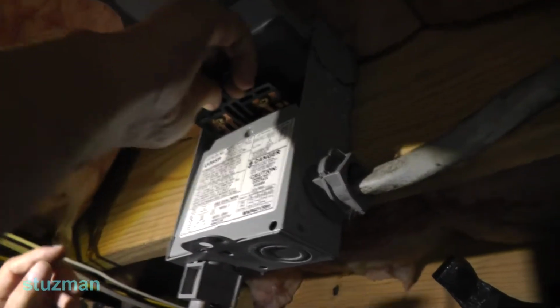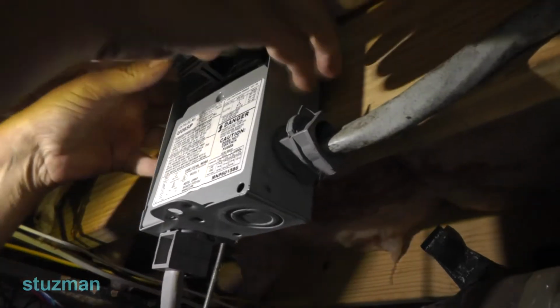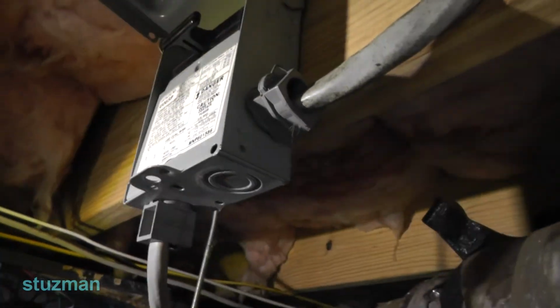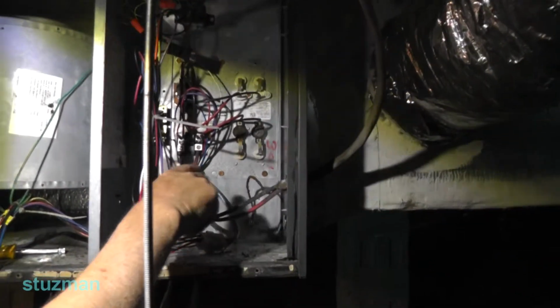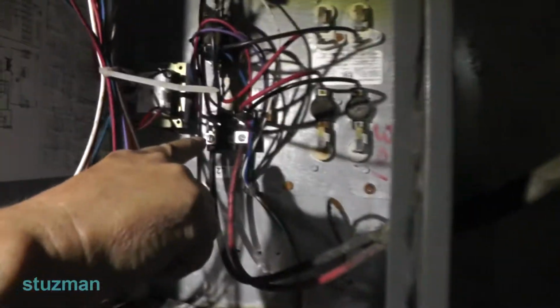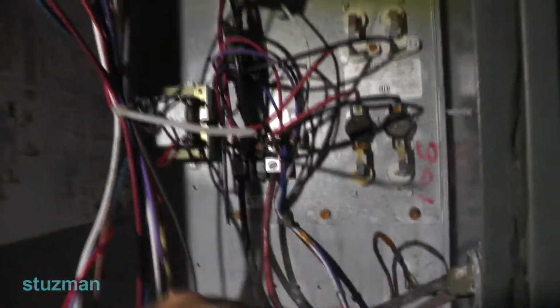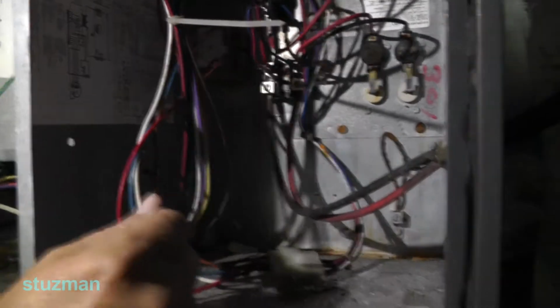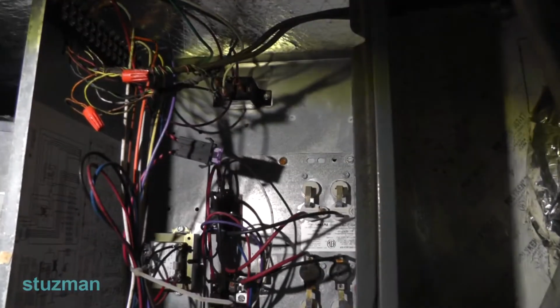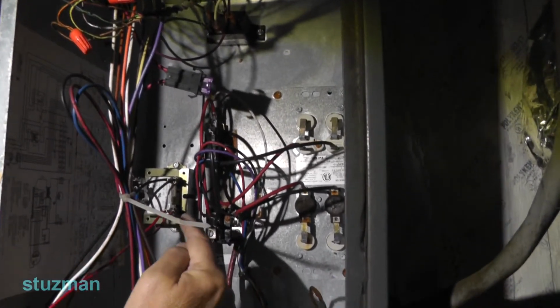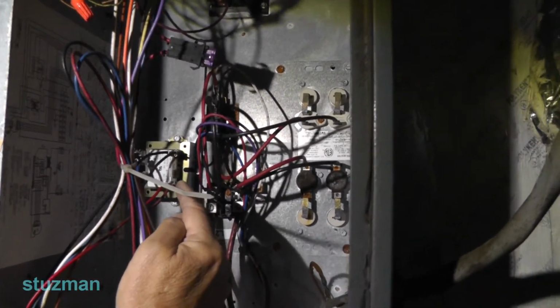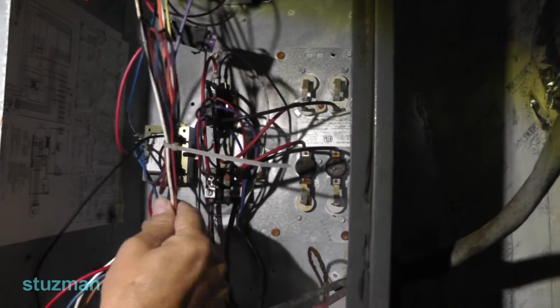So let me just stick him on in there. All right. Now, that puts the 240 volts. Here's my line power coming in. There's the 240 volts. You see it's going up there to the power distribution terminal box. You can see it's on this black and that red wire. Here's a control fuse. That's for the 24 volt AC. You see there's a step down transformer right in here. 240 volts on the primary, 24 volts on the secondary. That's over on that side.